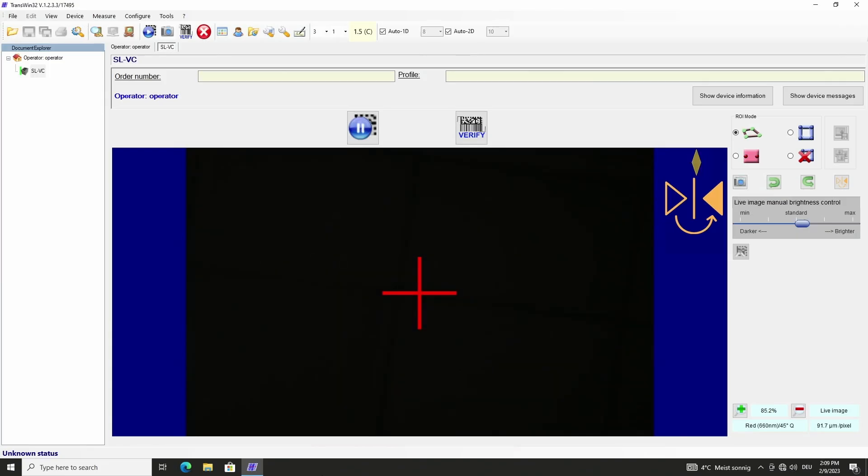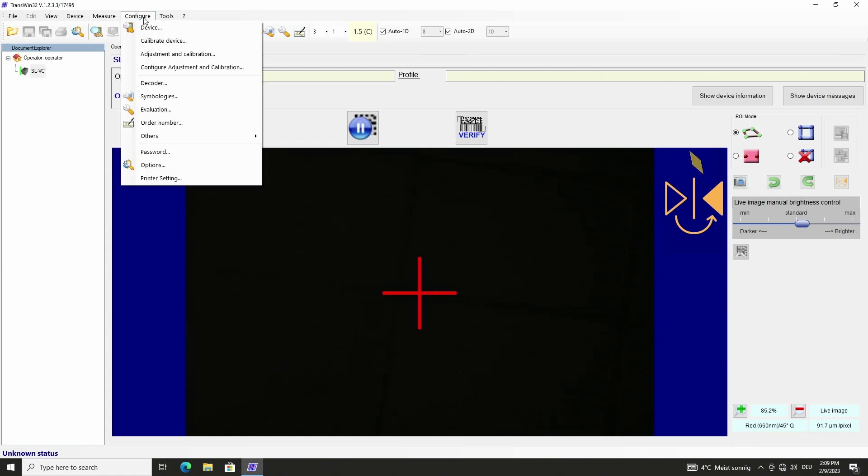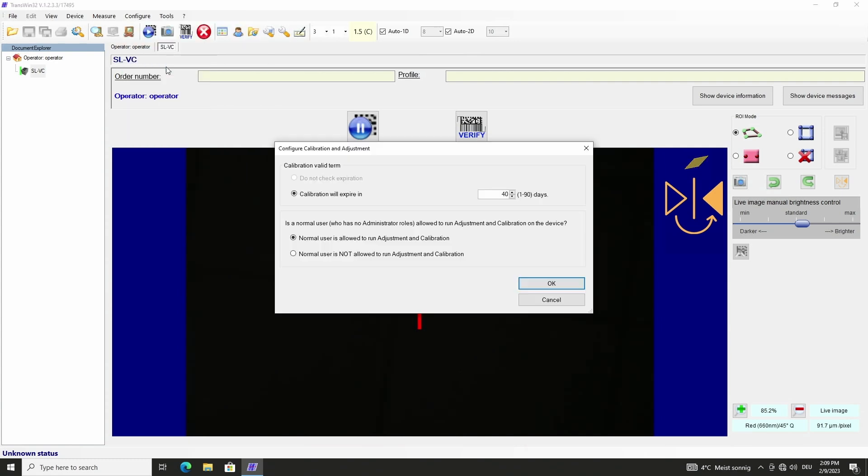The software is started and VIA VariCube is ready for operation. In menu configure, configure adjustment and calibration, I enter how many days calibration will be valid. I can enter up to 90 days but we recommend to do the calibration monthly. Supplemented with a buffer it is 40 days.